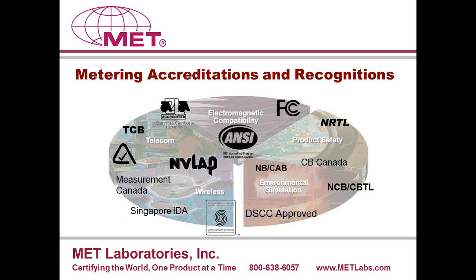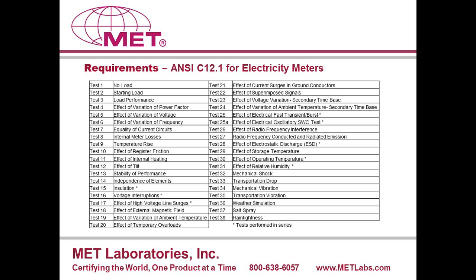Okay, so getting down into the details of the requirements for ANSI. Basically, there are 38 tests that are required by the ANSI C12.1 or the C12.20 standard for electricity meters. The primary difference between C12.1 and C12.20 is that C12.1 is for meters that are basically 1% accuracy or higher, and C12.20 contains requirements for meters that are 0.2% or 0.5% accurate. So it's a tighter accuracy. And frankly, most of what we see anymore is tested to the C12.20 set of criteria because the revenue generation meters have a higher, tighter accuracy.